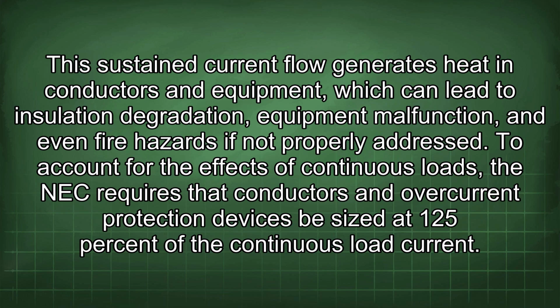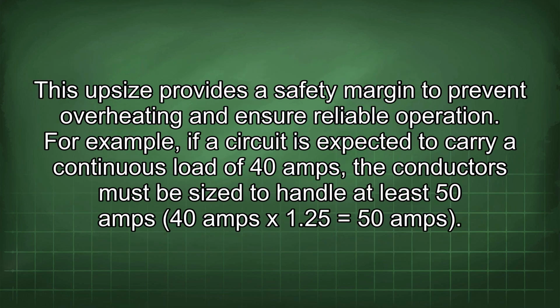To account for the effects of continuous loads, the NEC requires that conductors and overcurrent protection devices be sized at 125% of the continuous load current. This upsize provides a safety margin to prevent overheating and ensure reliable operation. For example, if a circuit is expected to carry a continuous load of 40 amps, the conductors must be sized to handle at least 50 amps: 40 amps × 1.25 equals 50 amps.